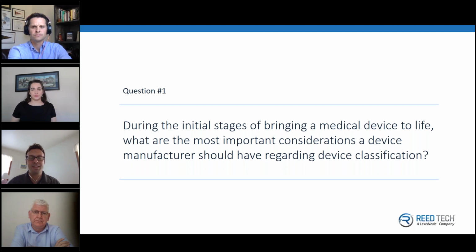Yeah, I agree with getting ahead, definitely from a UDI registration perspective as well. As early as you can, have a look at what, depending on which markets you're going to be selling the device in, the different market requirements are with respect to the UDI databases, just so nothing surprises you. Many times it's the last mile of making the registration to the GUDID, but just know what you're in for once you do get to that stage.